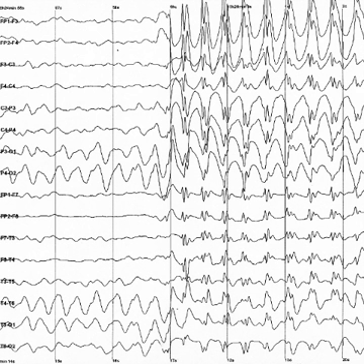Furthermore, currents can be induced in moving EEG electrode wires due to the magnetic field of the MRI. EEG can be used simultaneously with NIRS without major technical difficulties. There is no influence of these modalities on each other, and a combined measurement can give useful information about electrical activity as well as local hemodynamics.